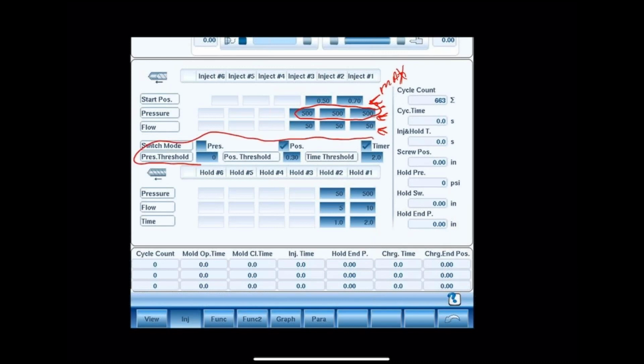The middle section here is your cutoff or your switch over. You can actually choose all 3 if you'd like, or you can just choose 1 or 2. It doesn't matter. And what happens is the first one that it sees is going to go into cutoff. So whatever it sees first, let's say your injection was 3 seconds, but you have your timer at 2 seconds, once it hits 2 seconds it's going to drop to the hold right away.